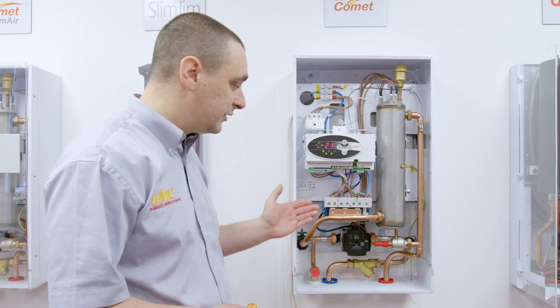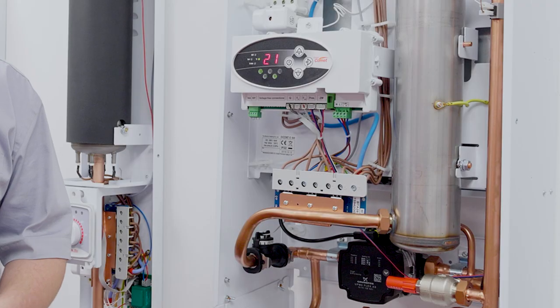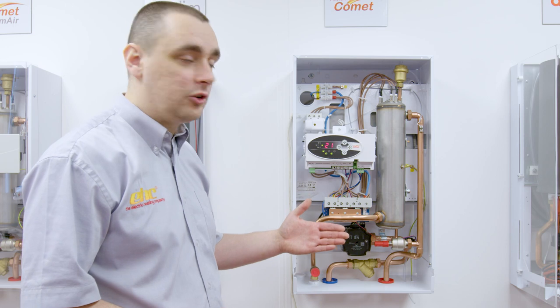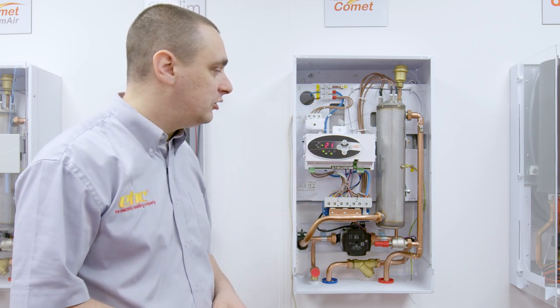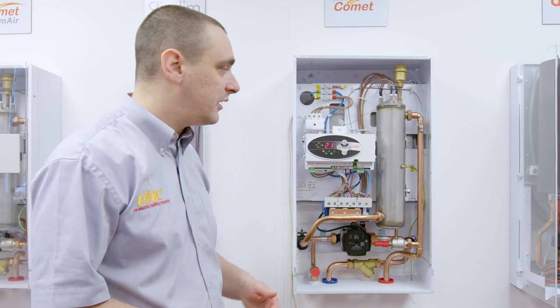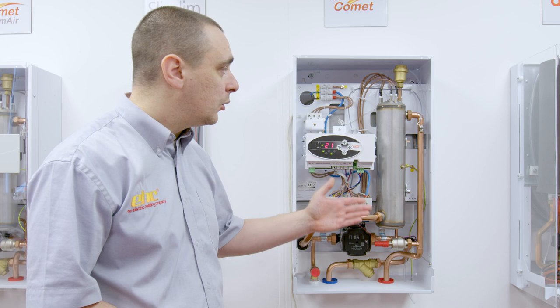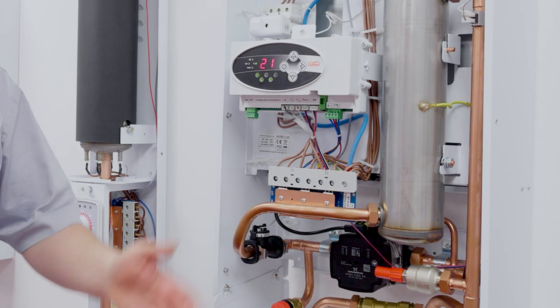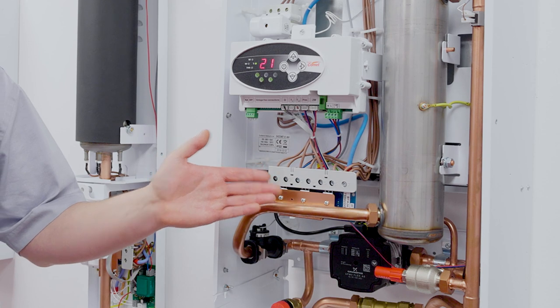This circuit board is easily tested with the use of a multimeter or digital voltage tester. Another issue would be a failed element within the heat exchanger where it is a short to earth, however the resistance is high enough that it will not take out the breaker. For this purpose we look to do an insulation resistance test on the terminals of the power board through to the elements themselves.